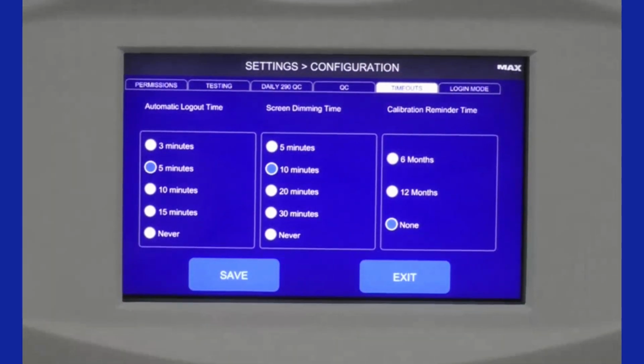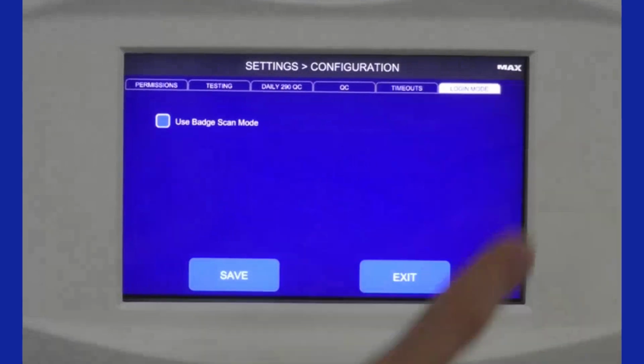And then this menu just has some basic options around automatically logging different users out, dimming the screen just to save energy, and then a calibration reminder, right? So for our osmometers here at Advanced Instruments, we typically recommend calibrating every 6 months or as needed, right? If your result is outside of your acceptable QC range and you feel it's time to calibrate, then you would calibrate. But you could also designate a reminder at the 6-month and 12-month mark using this instrument as well. So a nice little message will pop up letting you know.